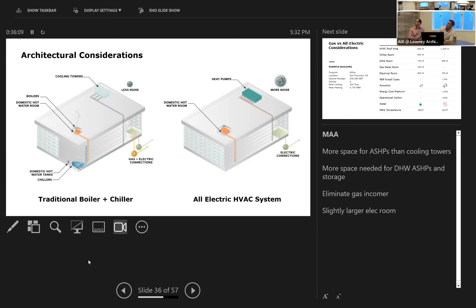The domestic hot water on the left would be done with a regular gas-fired domestic hot water heater. The one on the right is a heat pump water heater. And what we find is that the heat pump water heaters will be married up with a larger amount of storage. It's to keep the cost of those heat pumps down, you use more storage. So your domestic hot water room will probably be a bit bigger than you're used to. On the positive side, you no longer have an indoor chiller room or a domestic hot water storage tank room. The other benefit, of course, is that the gas has gone altogether. So you've only got an electric incomer on the right, whereas on the left, you've got an electric incomer and a gas utility.